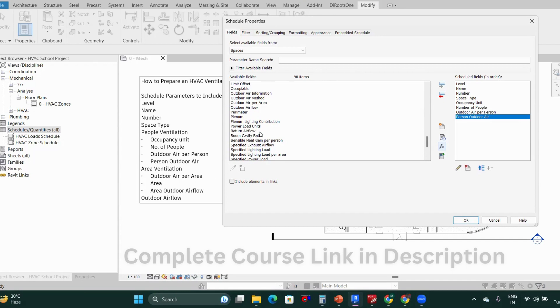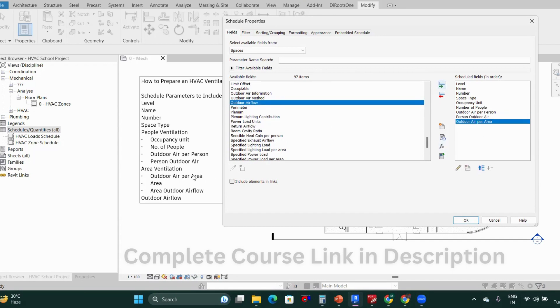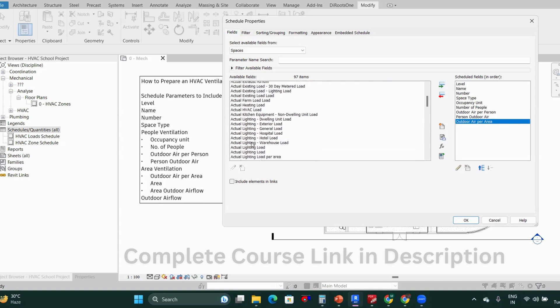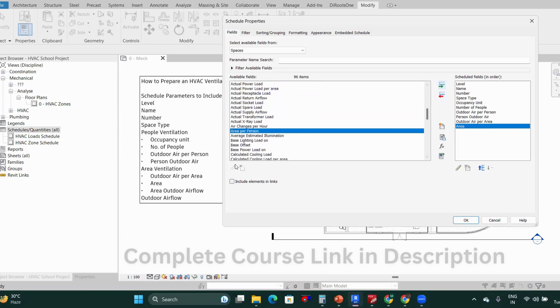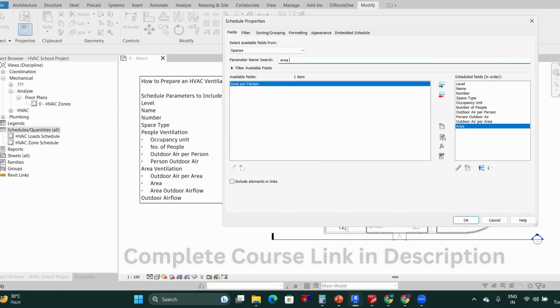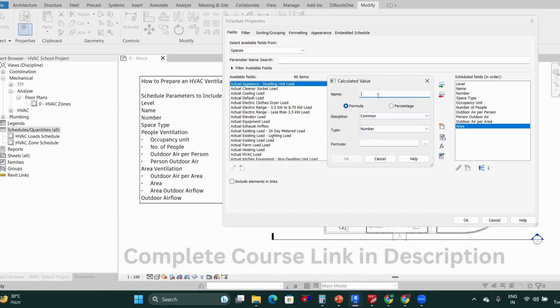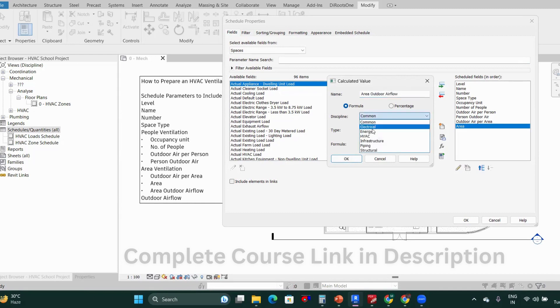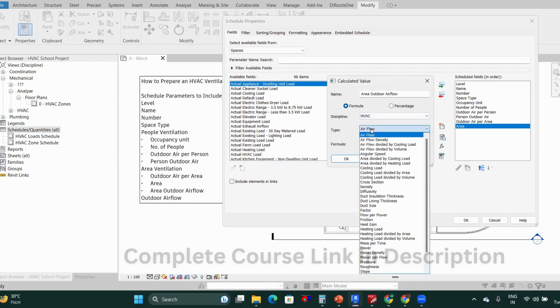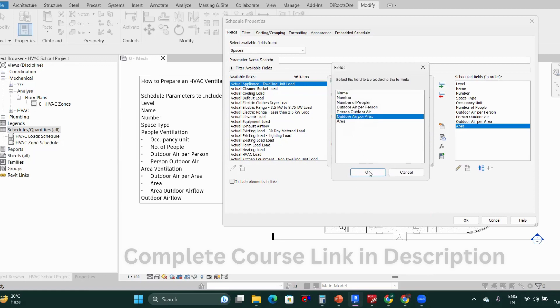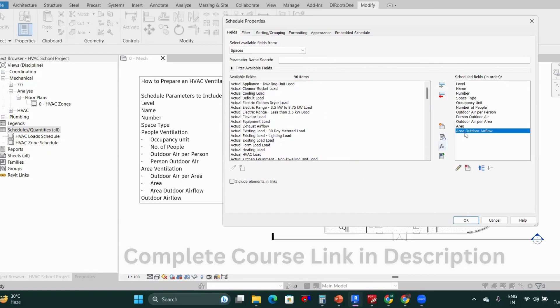Then we have outdoor air per area, which we already have in the schedule. Then we have the area parameter. The area outdoor air flow is a calculated parameter — it's not available directly. You multiply outdoor air per area by the area to get it. Create this parameter: name it 'Area Outdoor Air Flow,' HVAC discipline, type is air flow, formula is outdoor air per area multiplied by area. Click OK and you will get the area outdoor air flow.